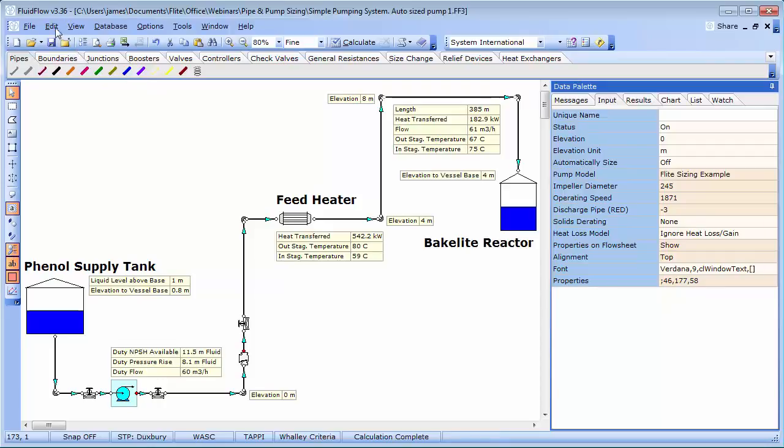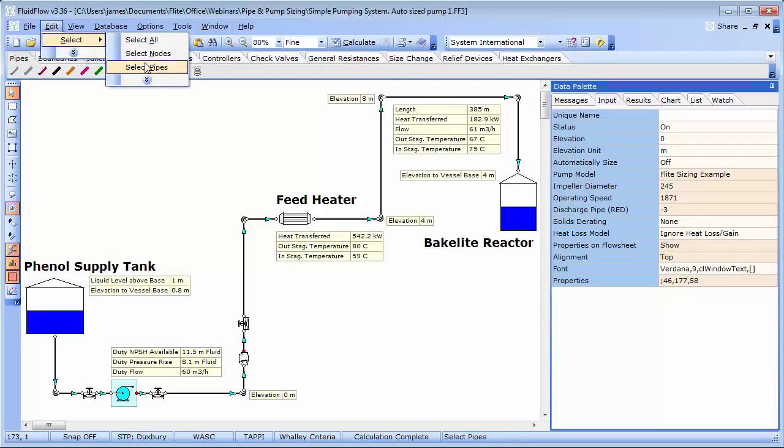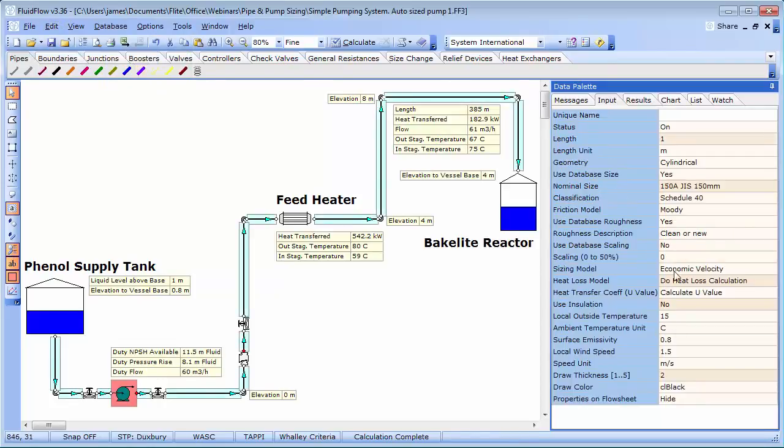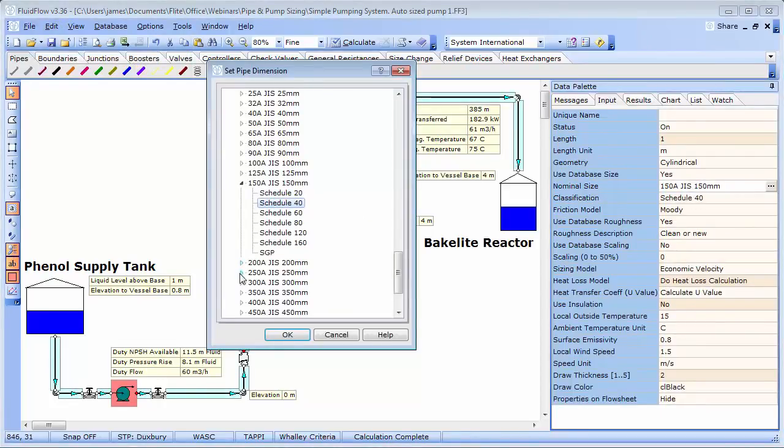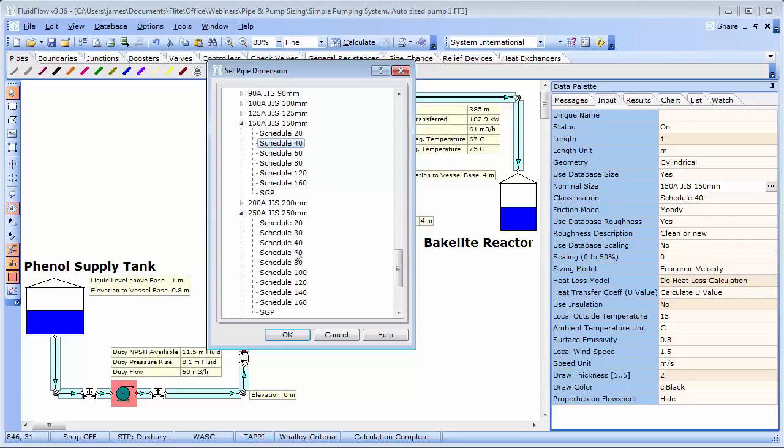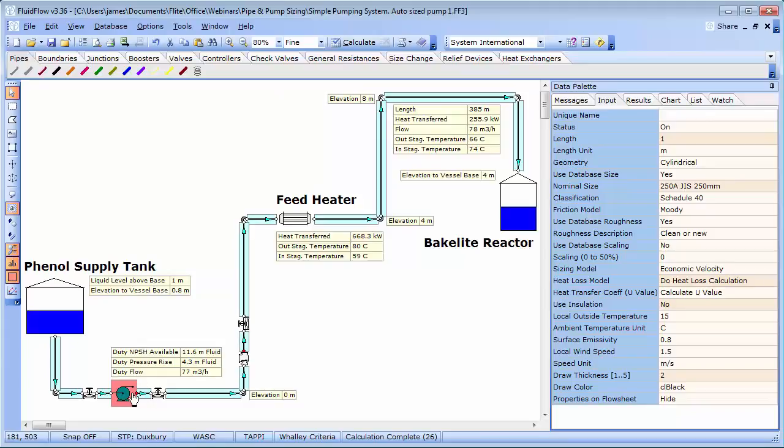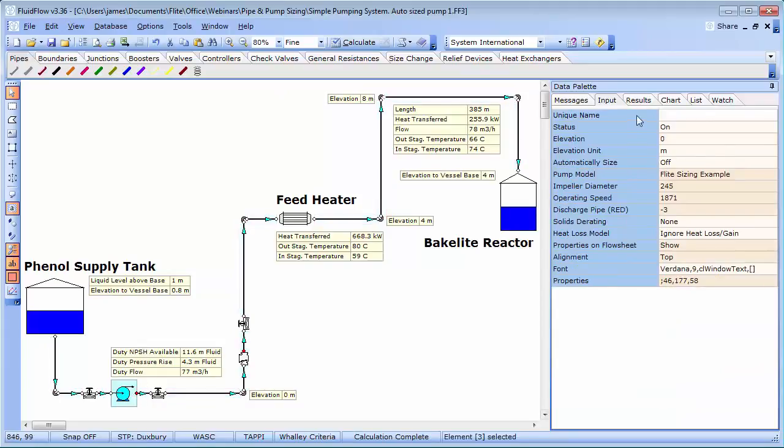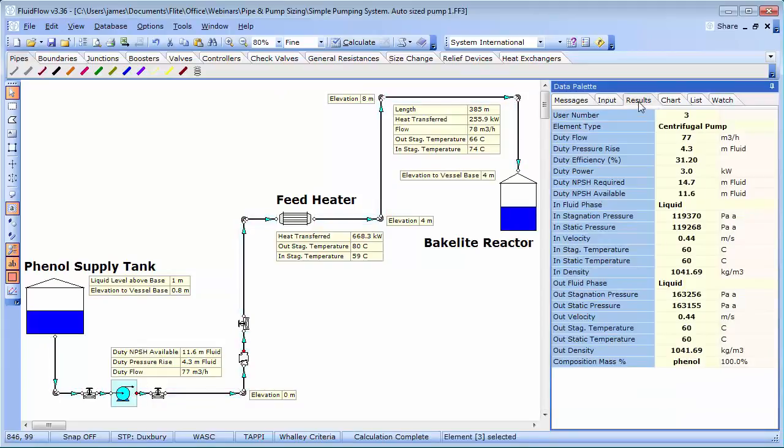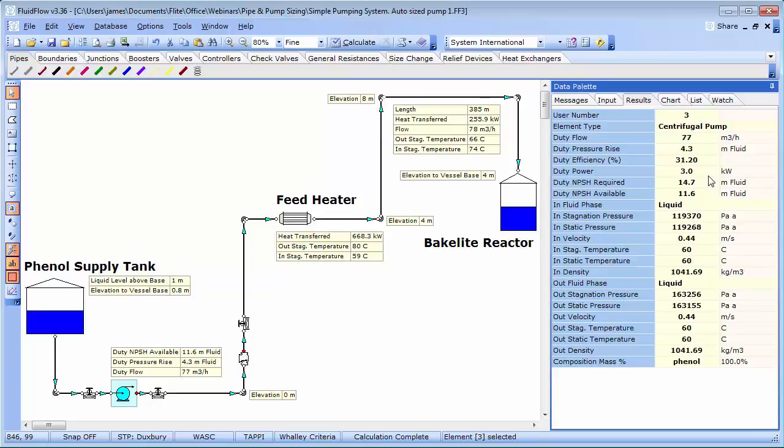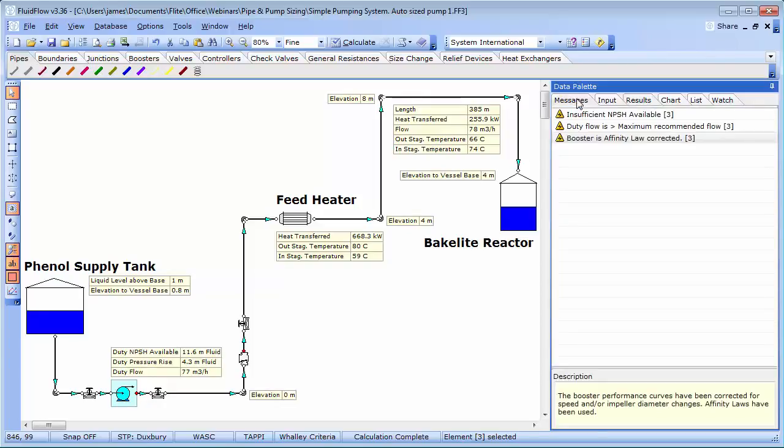As we can see, the pump efficiency drops off to 31%, and the power requirement increases to 3 kW. You may also note that we now have warning messages for the pump. So what could possibly be happening?